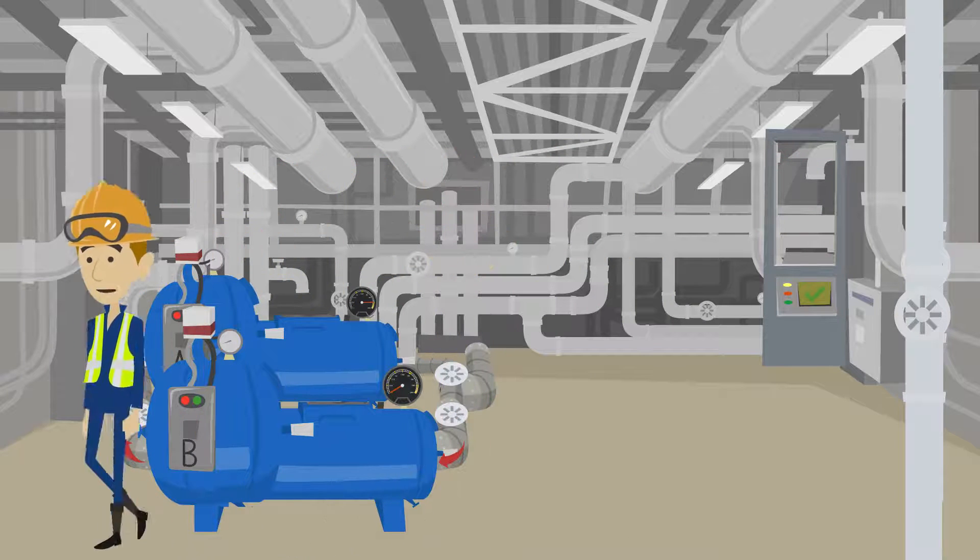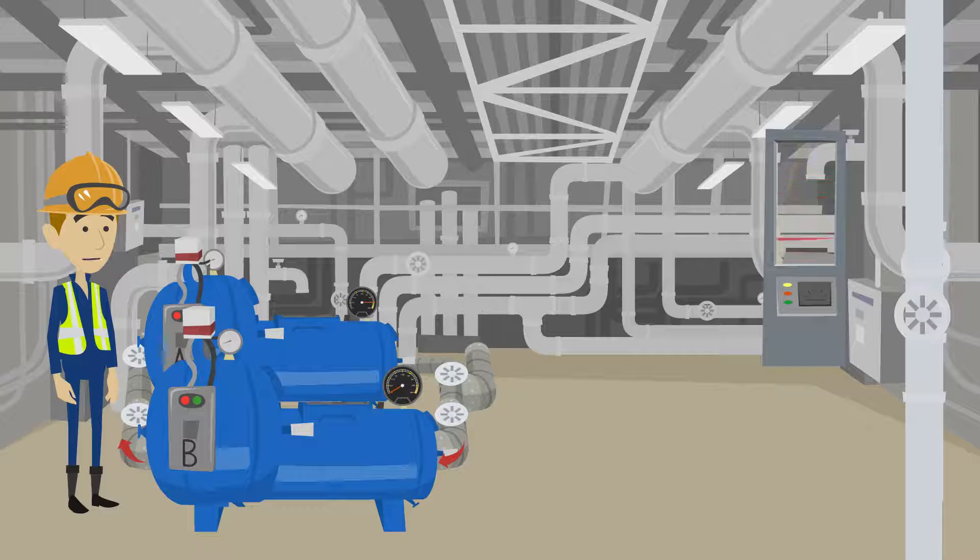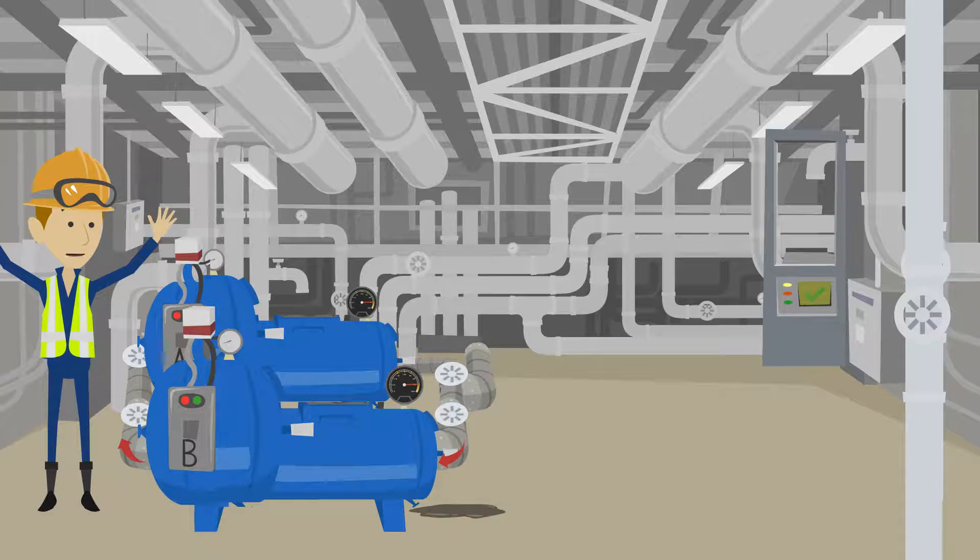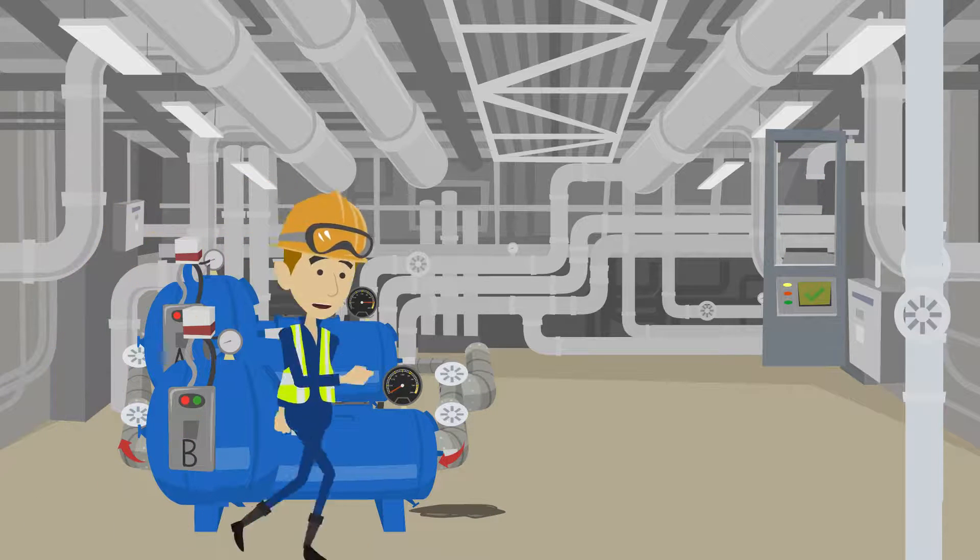I don't want to cause a blocked flow overpressure, so I'll open the discharge of the pump before I start it. Oh no! Now the upstream piping is leaking! I better close this off again and figure out what's going on.